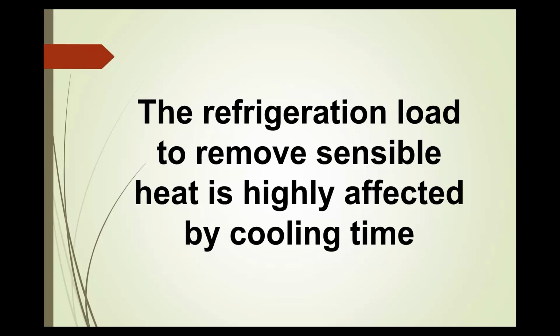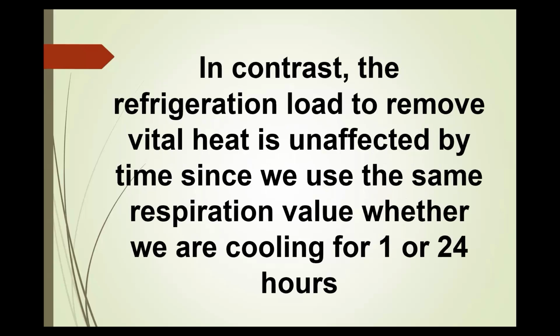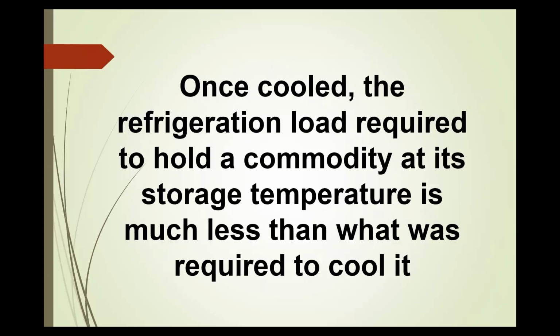The refrigeration load to remove sensible heat is highly affected by cooling time. In contrast, the refrigeration load to remove vital heat is unaffected by time, since we use the same respiration value whether we are cooling for 1 or 24 hours. Once cooled, the refrigeration load required to hold the commodity at its storage temperature is much less than what was required to cool it.